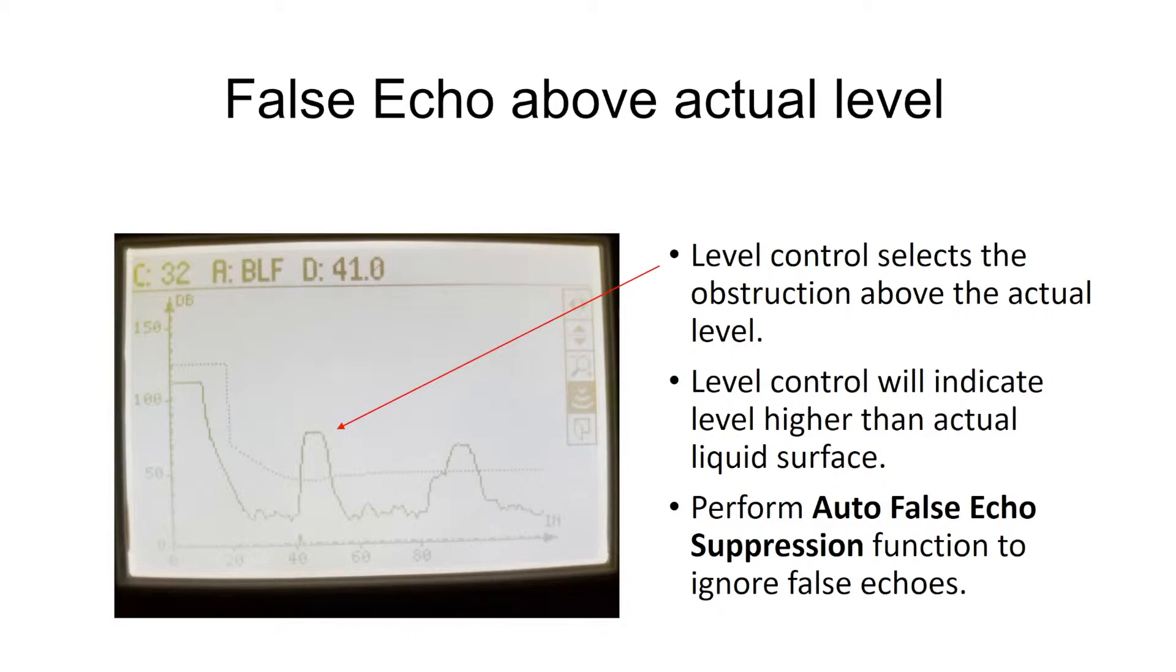Here's an example of an application where we have a false obstruction above the actual water level. This could be ladder rungs, it could be a pipe, it could be a concrete wall in a lift station, it could be many things. But in this particular application, the first echo going downward is a false echo from some type of obstruction, and the echo from the actual level is below that. Since we have a very strong echo from this false obstruction, the level control thinks that's our level. So, what do we do to get rid of it?